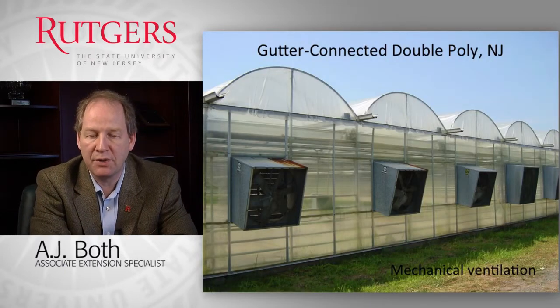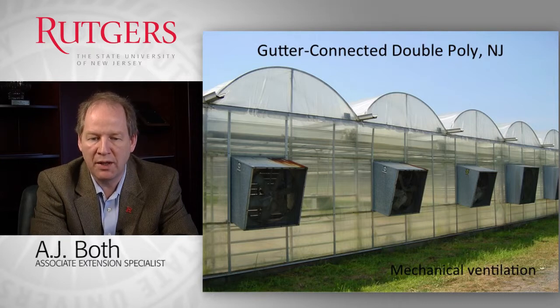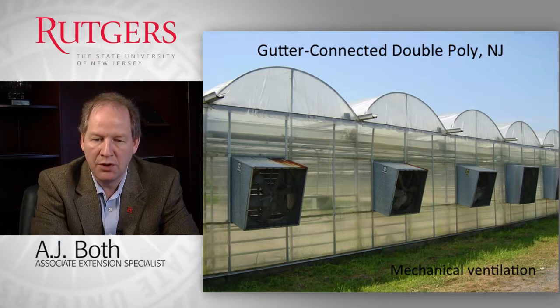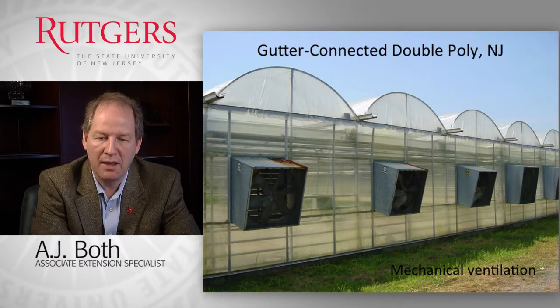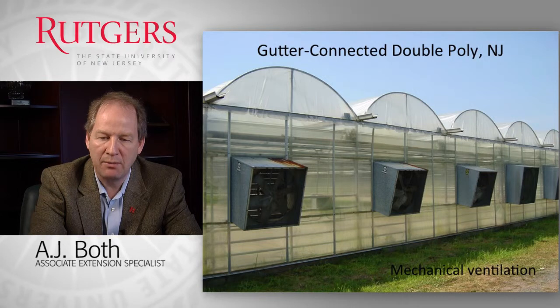An example of a gutter-connected greenhouse: we use this compared to the freestanding hoop style to reduce the total surface area. In this case it's a heated greenhouse with a ventilation system. We reduce the unit surface area per unit growing space and thus reduce the heat loss per unit growing space, saving energy compared to freestanding houses. Although freestanding houses can be individually controlled, so sometimes it makes sense to have them. When you grow larger batches of plants that require similar conditions, gutter-connected houses can be very effective.